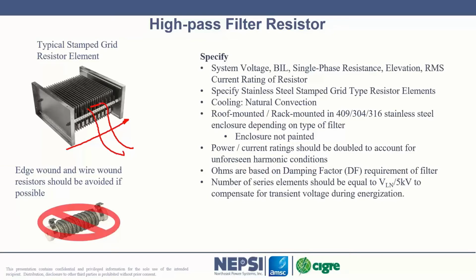Say I need to increase my dampening of the filter. Well, by putting a larger resistor in there, I can then tap my resistor down to a lower resistance value and improve the dampening factor. And so vice versa, by the way, it works in the opposite direction.